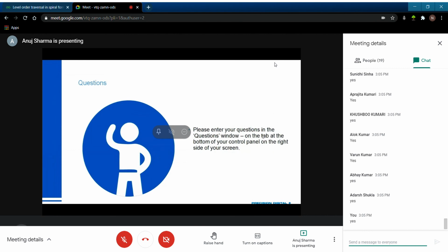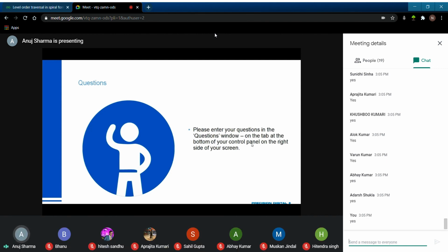His question is that he recently changed his turbidity transmitter from one that handles 0 to 1 NTU to one that handles 0 to 5 NTU over its 4 to 20 milliamp range. But he only measures from 0 to 0.15 NTU. So since then, the HMI and other equipment, his 4 to 20 milliamp signal has been fluctuating. Could that be noise or something related to a signal? Joe, what do you think?